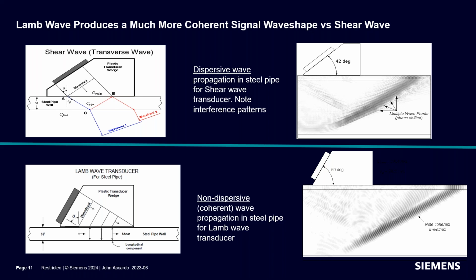So competitors will say, well, here's a transducer, you stick it on your pipe and you go. But you're not matching the characteristics of the pipe. The pipe is what determines what it needs. It knows what frequency it wants because that's its resonance. And also the material that it's made from determines what the phase velocity is. So the pipe is the transmitting mechanism.